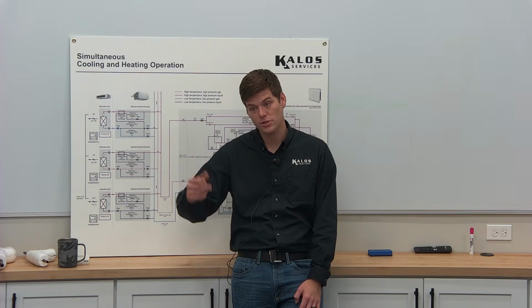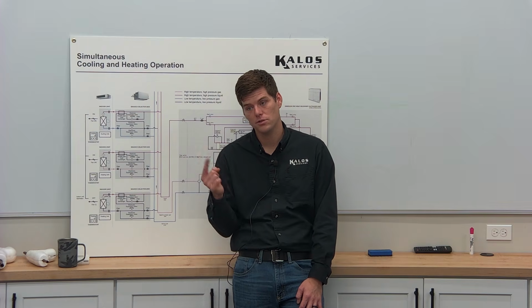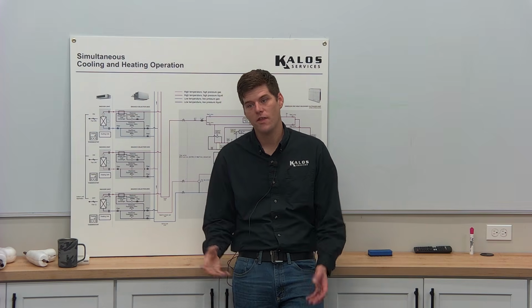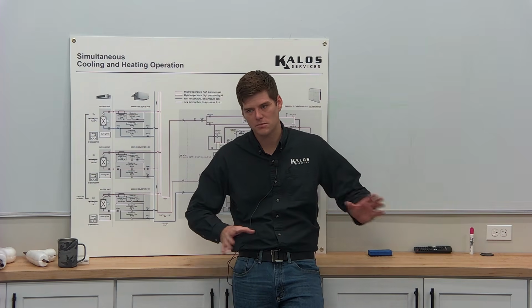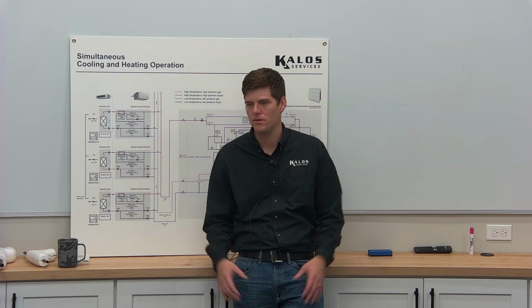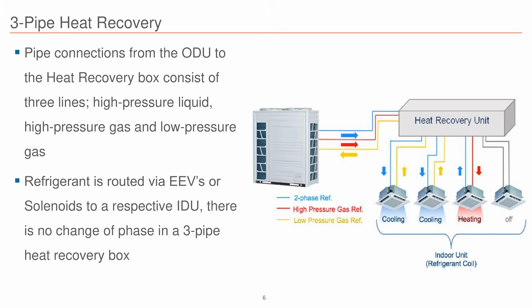So some manufacturers use electronic expansion valves because it's a slow close and then it's a slow open. And then they just have timers in between to slow the system down or like a wait period, if you will, like a hot start. So, and then you'll see 3-pipe here, right? Low pressure, hot gas, liquid.